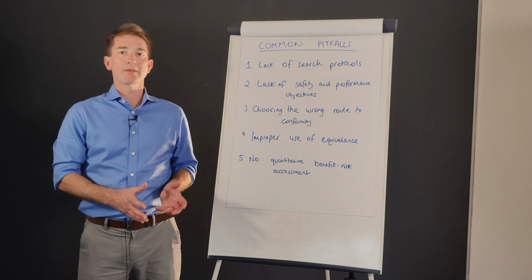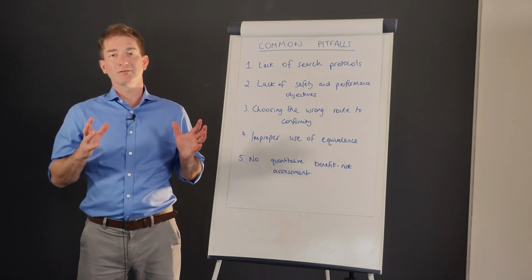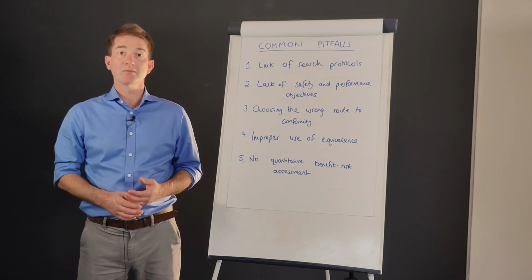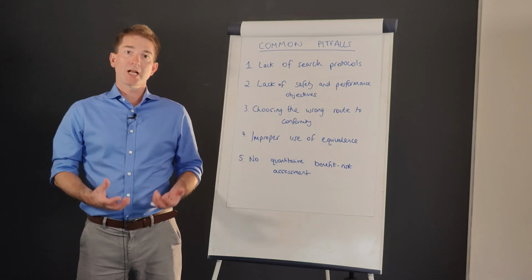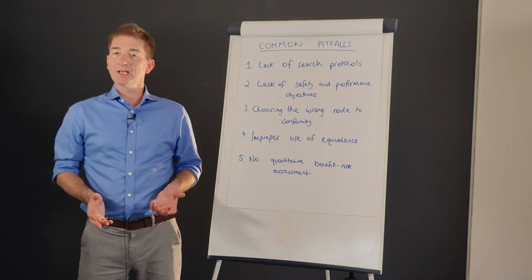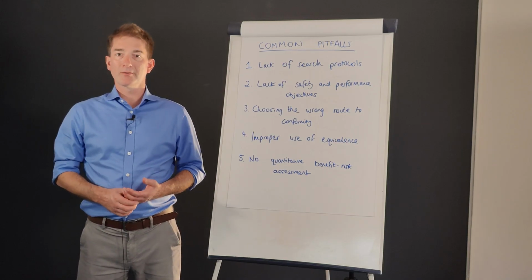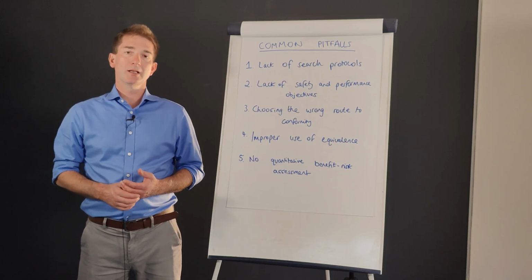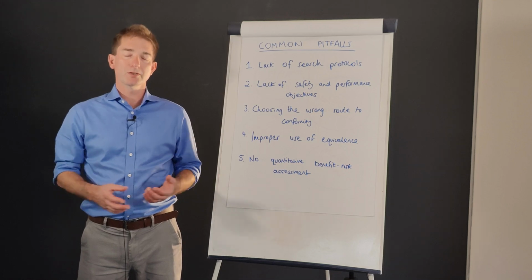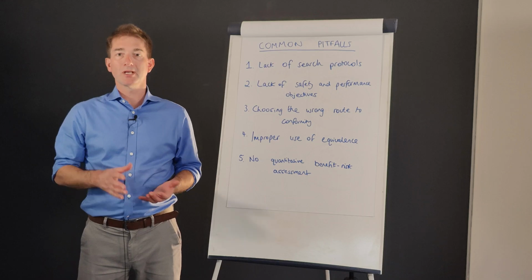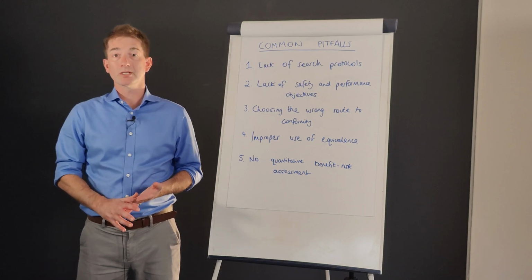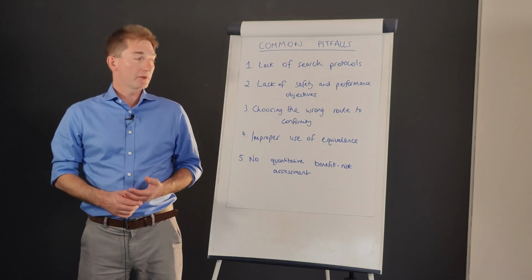And another area where this pitfall manifests is for devices that have successfully gone to market in the US through a 510(k), where substantial equivalence is a similar concept but relies only on technical characteristics, whereas for submissions in the EU, you need to also show similarity in biological and clinical characteristics as well. So it's much more difficult.